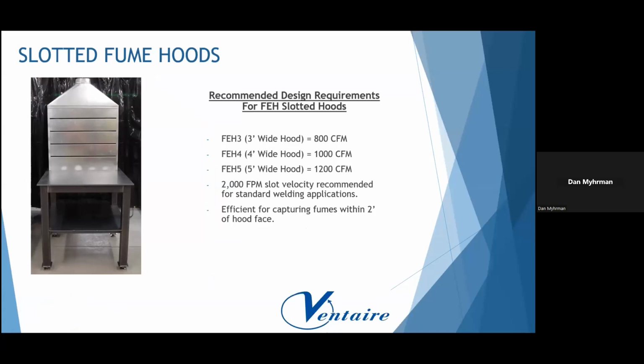I would say the only couple of downfalls about these hoods are they're only efficient to about 2 feet, welding out about 2 feet in front of the hood face. They also require a little bit more air than you would for a fume arm. As I mentioned earlier, a typical 6-inch fume arm requires about 600 CFM, and a 3-foot wide hood is about 800. So that's one thing to keep in mind.